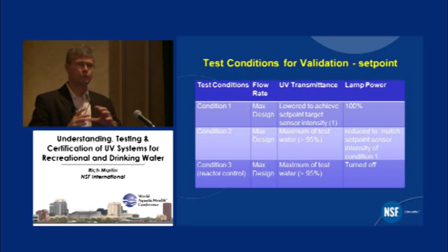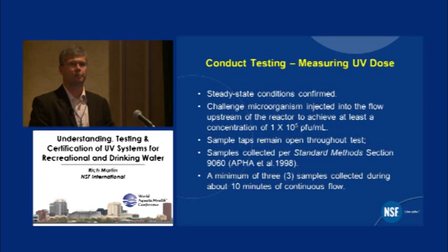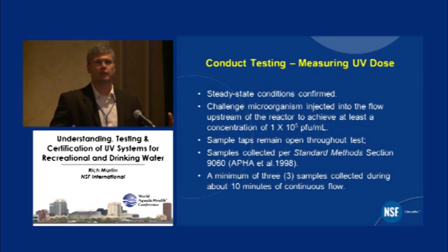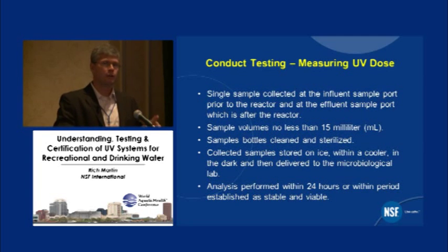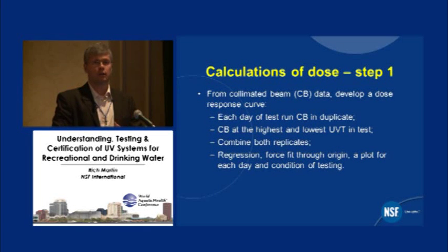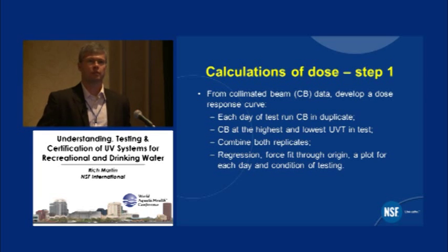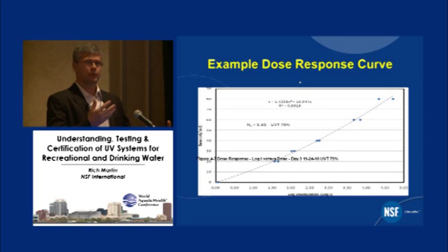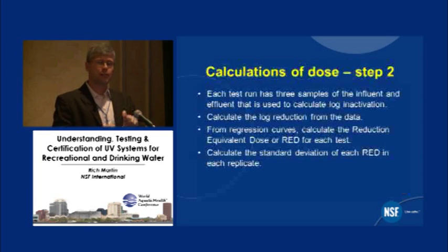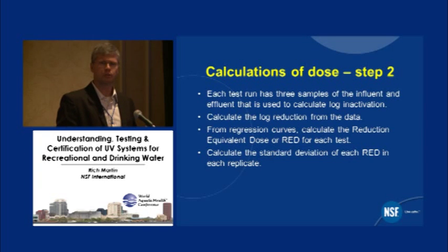But here's how we have looked at it, really based on how the industry has looked at it as well. The existing infrastructure of the products being tested and certified for a certain performance level is still relevant, but some uses or applications of UV systems might want an even higher level of performance to be verified. Especially in spray pads, where it's more likely that you're going to destroy the halogen or the residual disinfectants, and the only thing you have to fight against cryptosporidium is some other methodology, typically UV or ozone. So that's still in there, and there's no goal to remove the traditional tests.